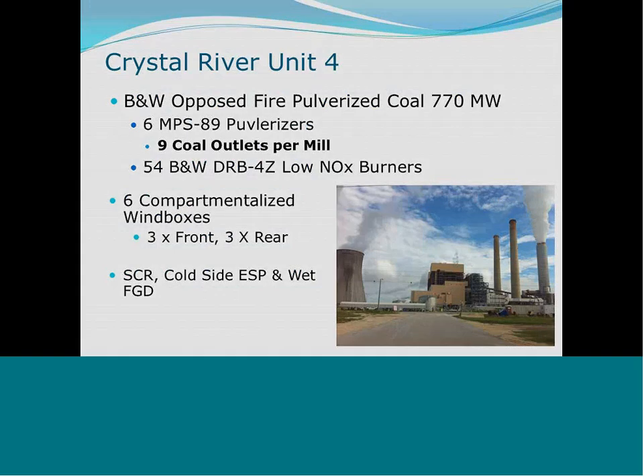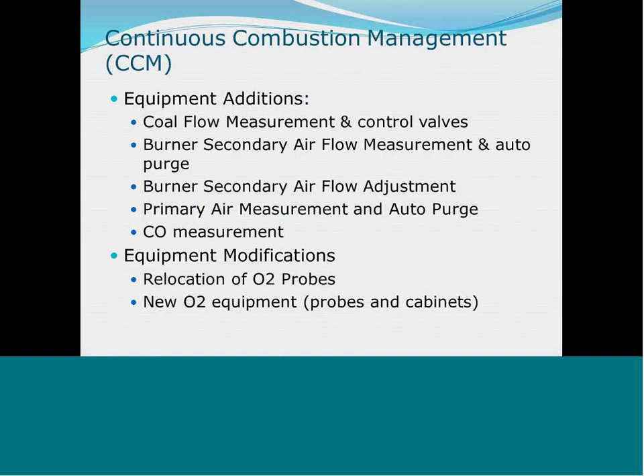The equipment that they added was coal flow measurement and control valves for each coal pipe, burner secondary airflow measurement with a purge, burner secondary air adjustment. The burners that they bought from the OEM did not have a drive on them. They were manually adjustable, so they put damper drives on them.